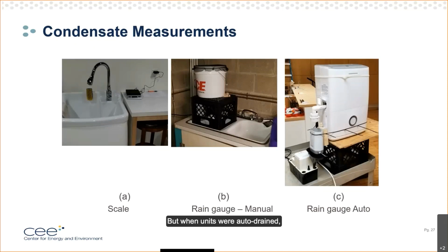But when units were auto-drained, we employed a third method: just a rain gauge placed right under the outlet of the unit, basically intercepting the hose. This allowed us to get continuous condensate measurements and better connect the energy use and operating conditions with condensate production.